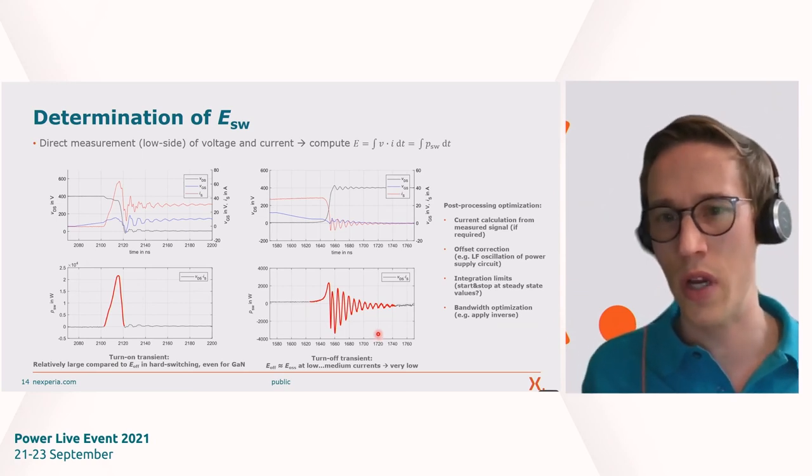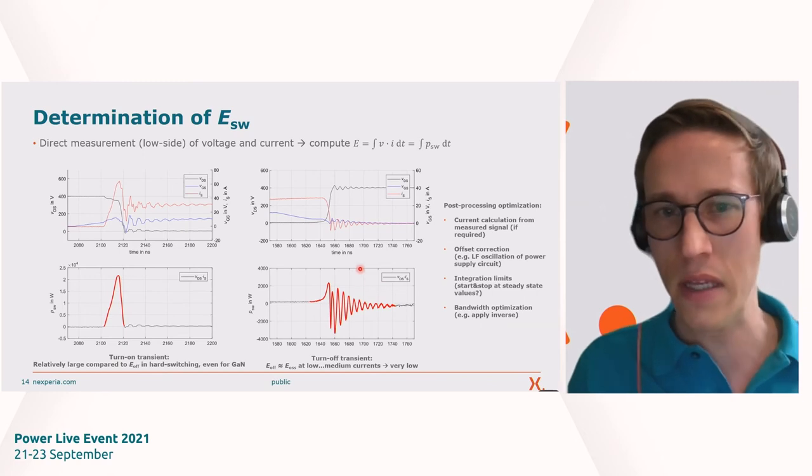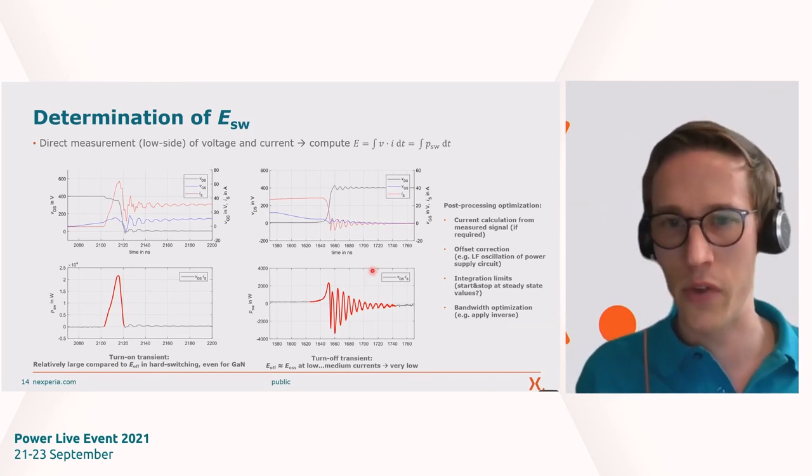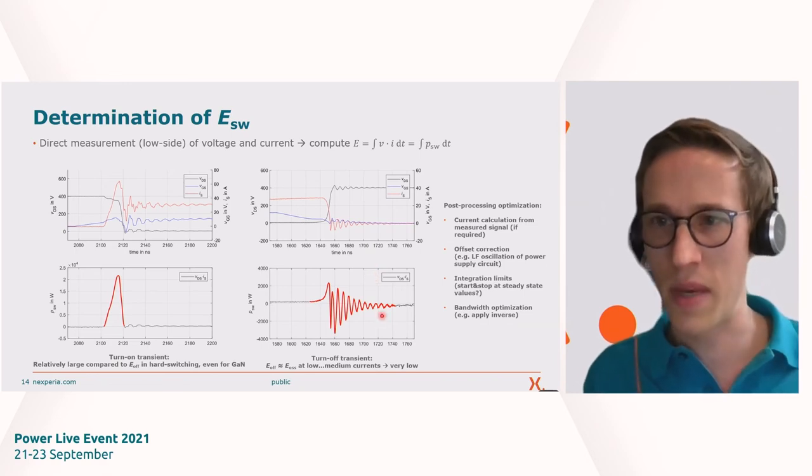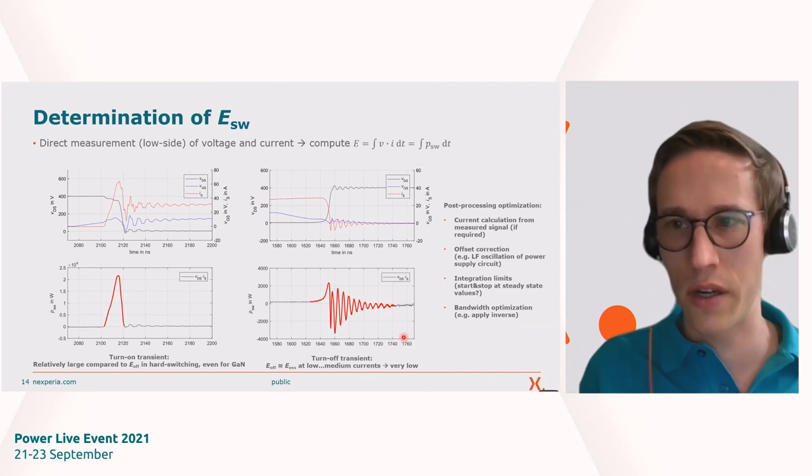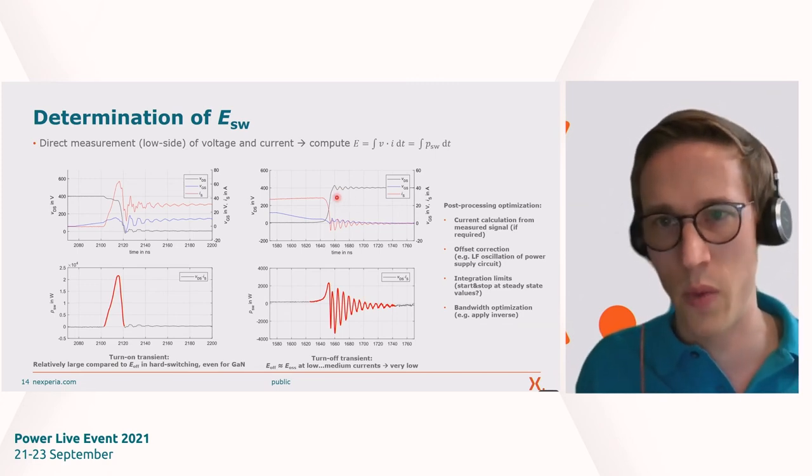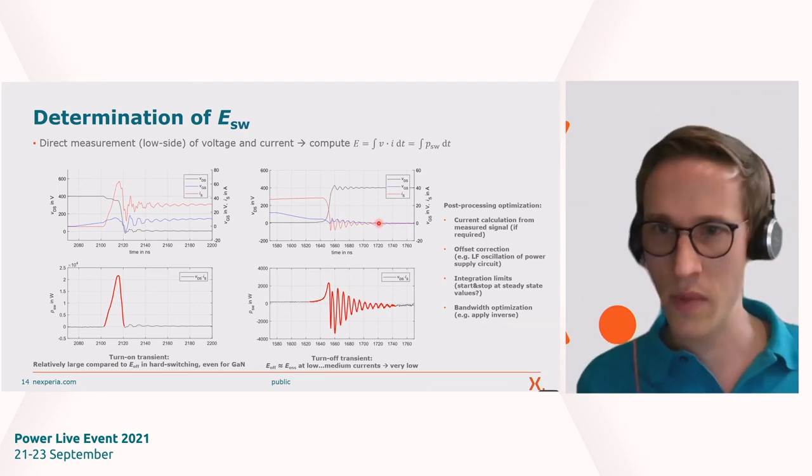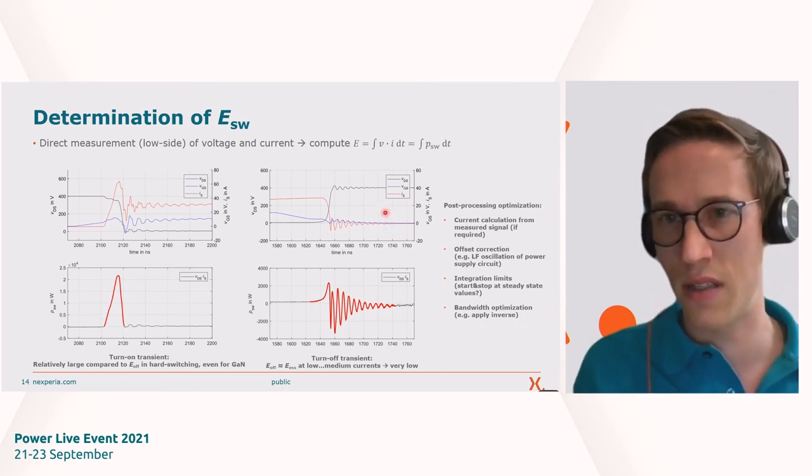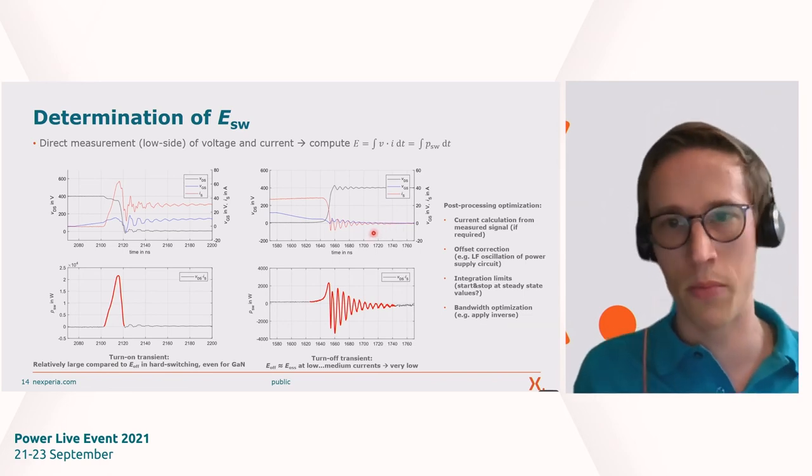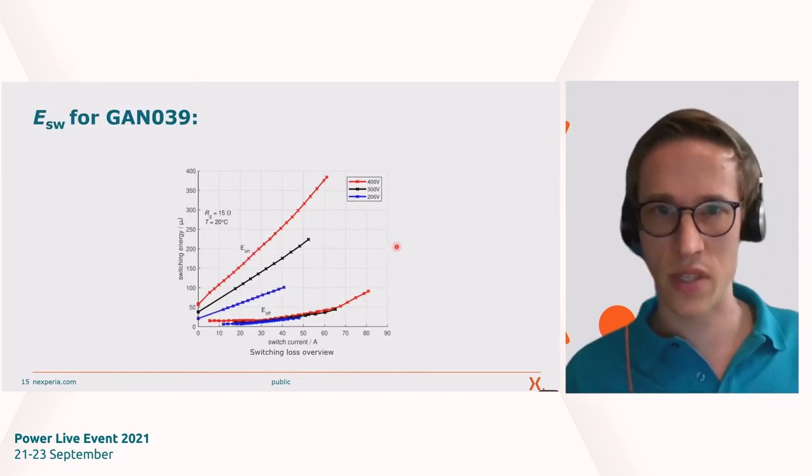Some examples are if you use a field sensor, for example, you will need to do some post-processing anyway, integrating the signal and removing offsets. But also, for example, if you do the test and have some low-frequency oscillation of the power supply circuit on your measurements, you might also need to correct that. Also, as mentioned, the integration limits have to be checked. Do we start and stop at steady-state values? Or will we capture some of the extra energy stored in our parasitics on the way? That will also lead to errors and needs to be prevented. Also, a very sophisticated thing to do, which is something that I don't do, but if you have clear knowledge about your measurement setup and your probes, you can also apply the inverse to improve the results. But this is something that I don't do at the moment because I think the results are already quite precise.